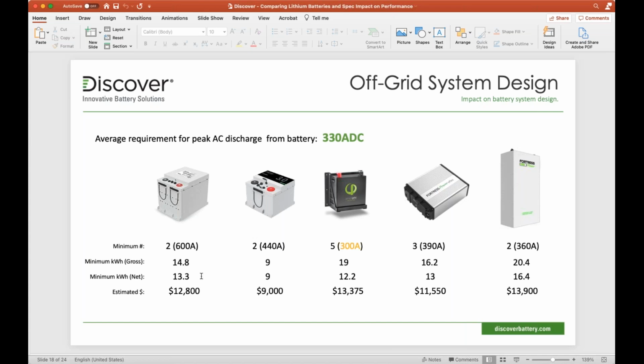Okay, all of these functions are driven by a combination of both the inverter's ratings and the amp current draw that you're converting to, and then what the current ratings of an individual battery are, because you're going to have to parallel those up to meet the minimums of the system requirement. Okay, it's a matching game, because in lithium you don't have this almost infinite ability to handle momentary currents, and you need to design your storage system based on the current rating of the BMS and the fundamentals of the lithium cells.